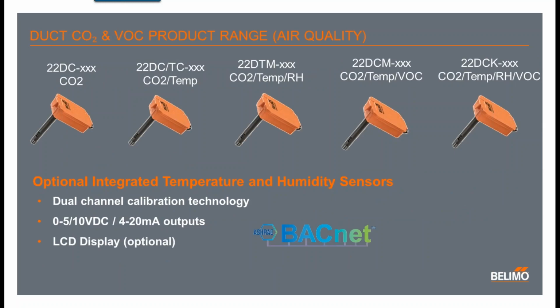Air quality sensors are available in many different forms and outputs. We can have a CO2 only. We can combine CO2 and temperature in one single unit, CO2, temperature and humidity. We can add VOC, and we can also have CO2, temp, humidity and VOC all in the one unit, all with 0 to 5, 0 to 10 volt outputs. The CO2 sensors are also available with milliamp outputs, and selected models are available with an LCD display. Selected models are also available with BACnet MSTP communicating.